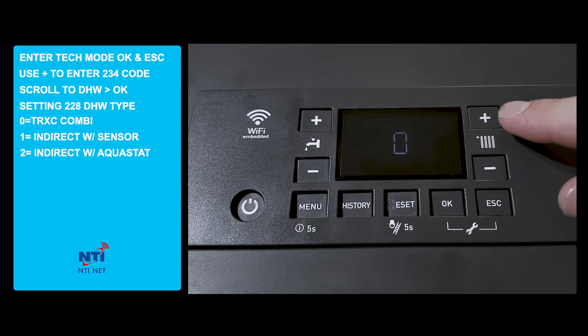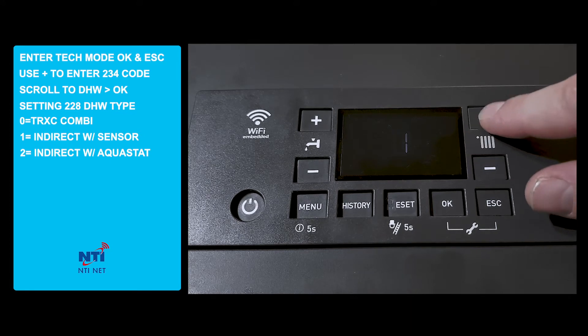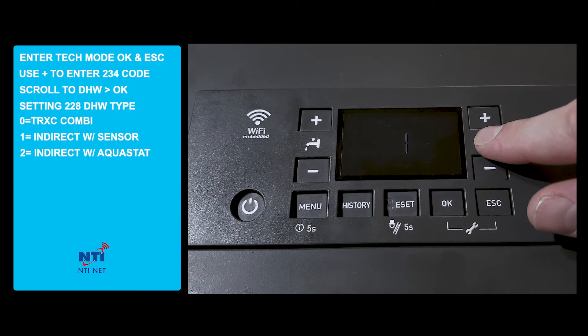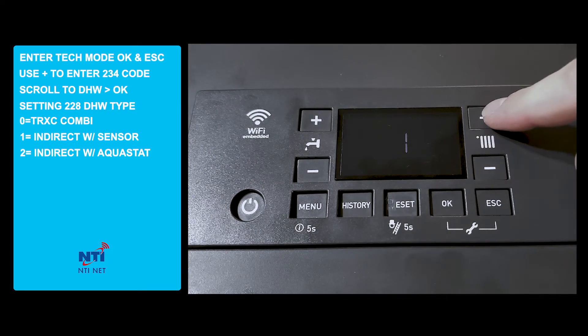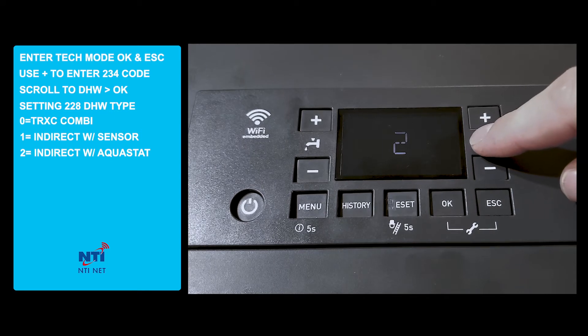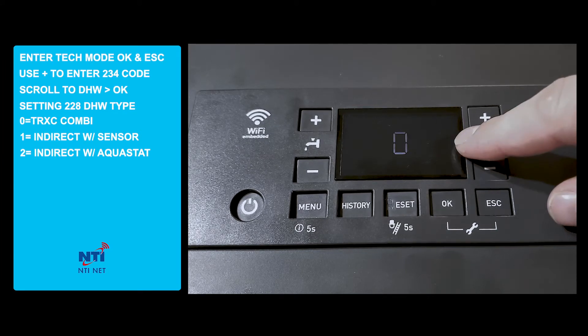We have three options. We have zero, which represents a combi boiler. We have one, which represents a boiler with an external indirect water heater using a tank sensor. And we have two, which represents an external indirect water heater using an external Aquastat control. In this scenario, we'll program it as a combi boiler.